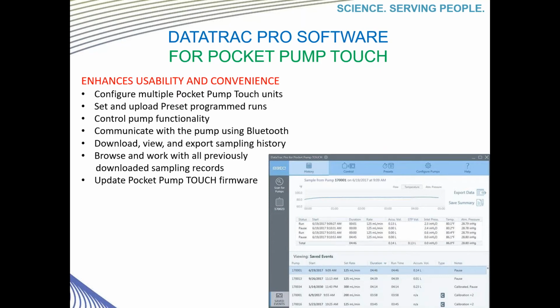The DataTrac Pro enhances usability and convenience of this pump. And I know a lot of people don't use software, but there are truly some great features in our DataTrac Pro software that might help you be more efficient and productive. For example, configuring multiple Pocket Pump Touch units by being able to send the same information to multiple units. You can upload preset program runs, as I mentioned earlier, to the pump. And I feel like this is a heavily underused feature of this and some of our other pumps as well. This gives you the ability to have multiple pumps start at exactly the same time, or even if it's just one pump, you can have it start and stop at exactly the times you need, even if you're not present.